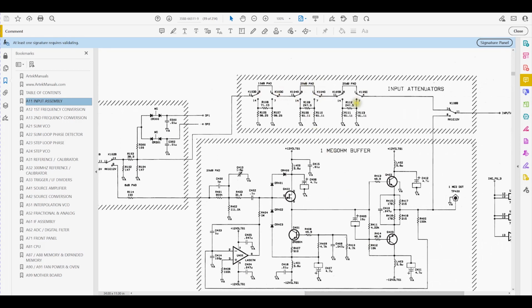K103B, K104B, and K105B. One of the most common failures of many spectrum analyzers and oscilloscopes is the failure of attenuator relays. Quite simply, they are the most used relay and wear out. They can either stick in position and or not make full contact on one or more poles. We will start checking these relays and see where that takes us.